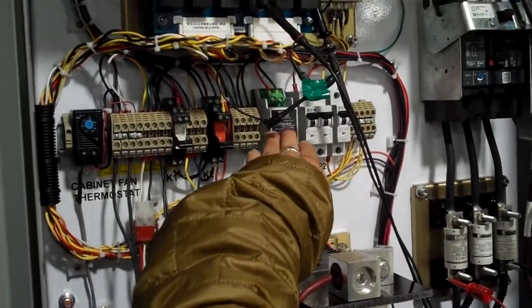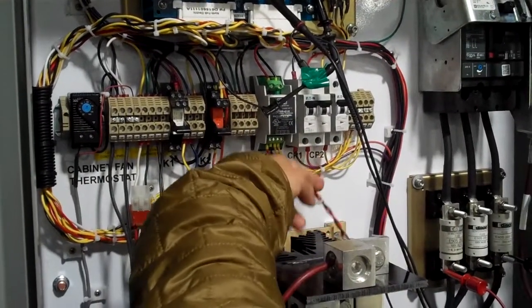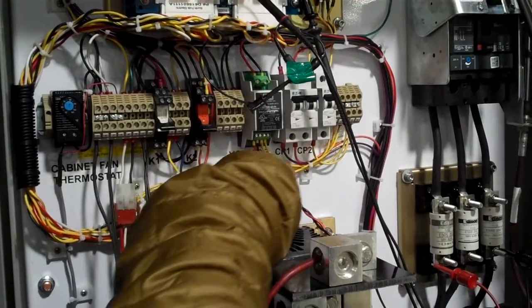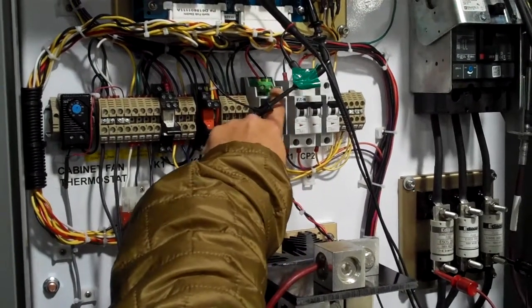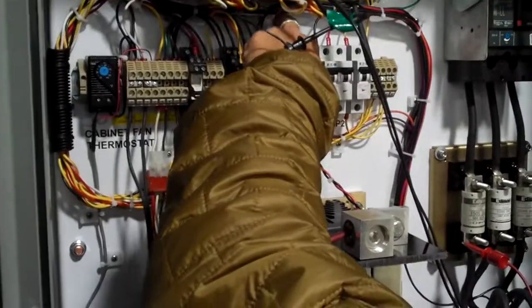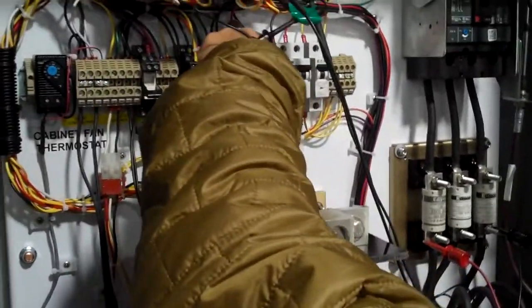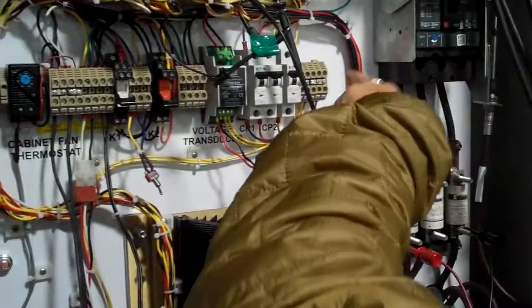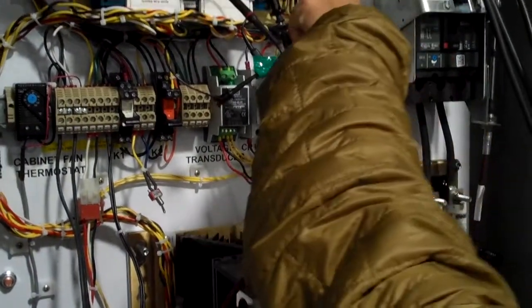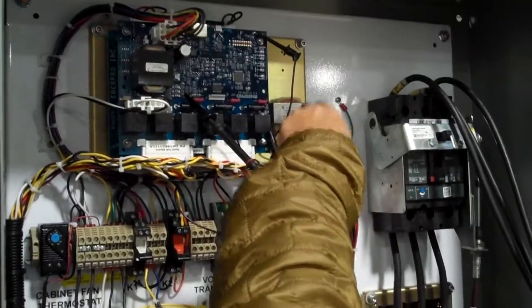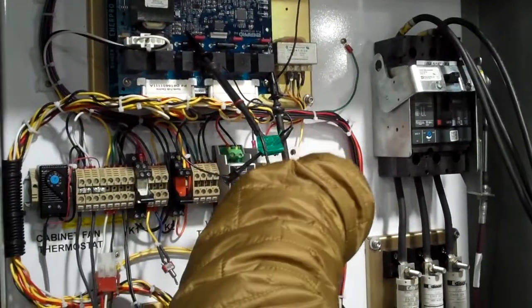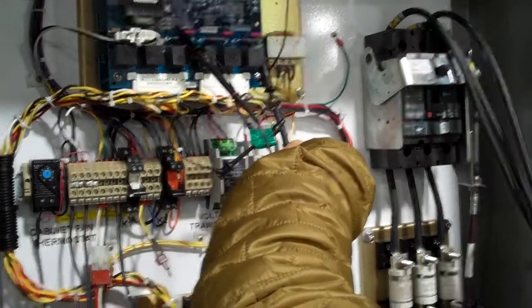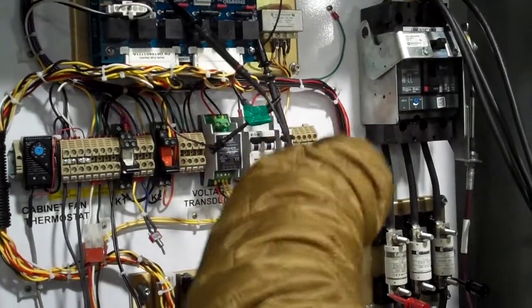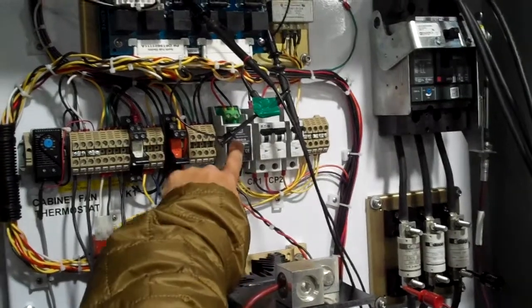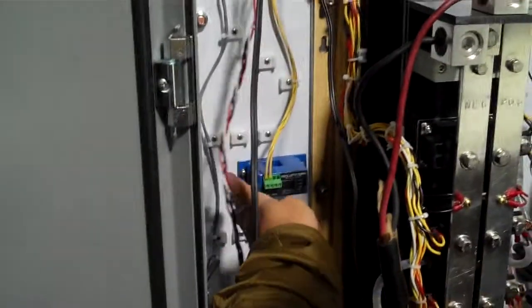And here we have our connections to our transducer. We're picking up the output. We are providing power, and then actually this is where we're bringing in the voltage from the bridge, and this is where we're picking up the 4-20 milliamps. And these are the connections from the line to the primary of the transformer, the secondary of the transformer. Both the input and the output are protected, and here's where we distribute the 24 volts to the voltage transducer, to the current transducer, which we have out here.